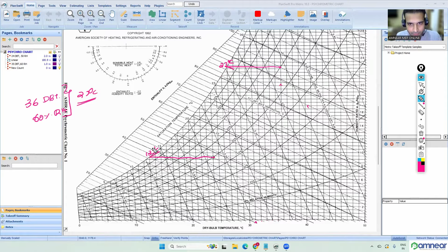So dew point temperature is simply a temperature, the temperature at which the moisture present in the air will start to condense. For example, for a room state of 24 degrees Celsius and 50% relative humidity, the dew point temperature is 11, 12, nearly 13 degrees Celsius. Every state has a dew point temperature. So whenever the air is cooled below the dew point temperature, the condensation will start. Understood? That's the basics. Now I can come to the point of why condensation happens within air conditioned spaces.